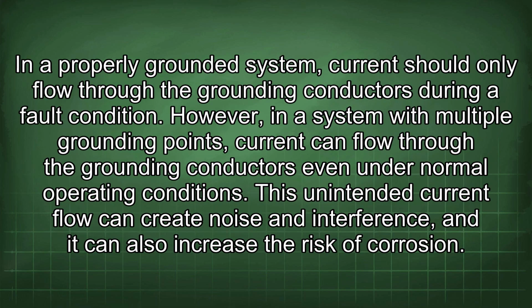Ninthly, the issue of unintended current flow can be significant. In a properly grounded system, current should only flow through the grounding conductors during a fault condition. However, in a system with multiple grounding points, current can flow through the grounding conductors even under normal operating conditions. This unintended current flow can create noise and interference, and it can also increase the risk of corrosion.